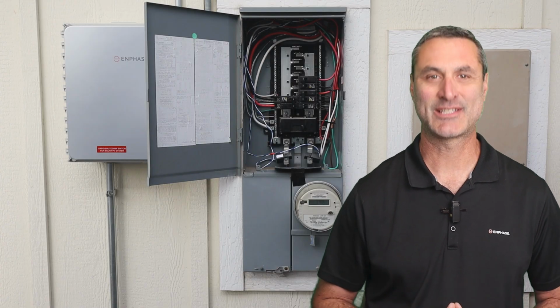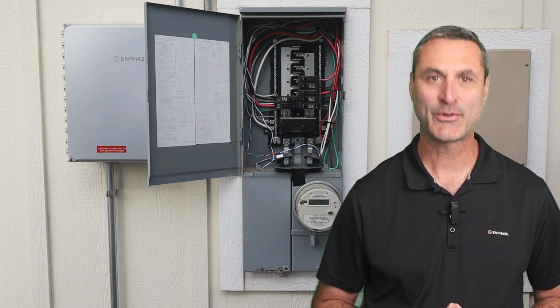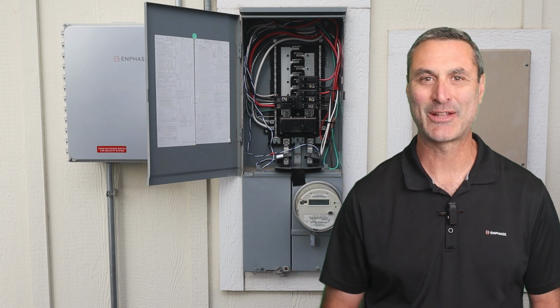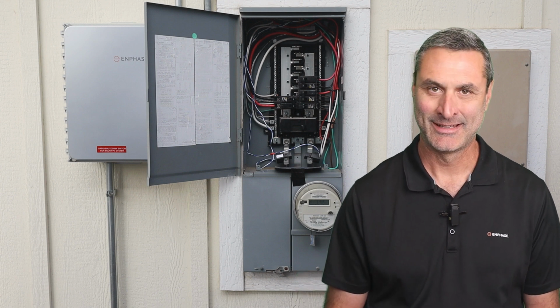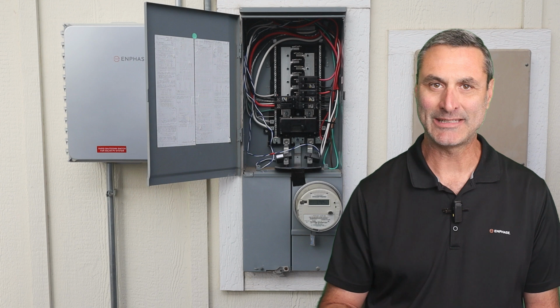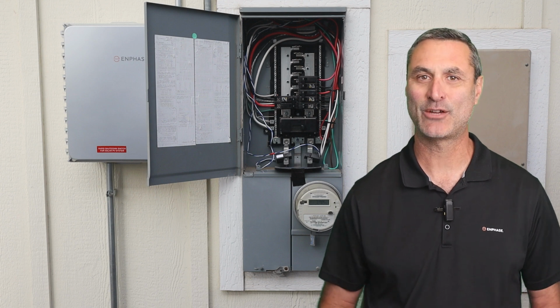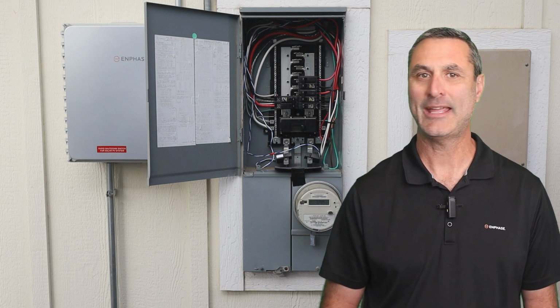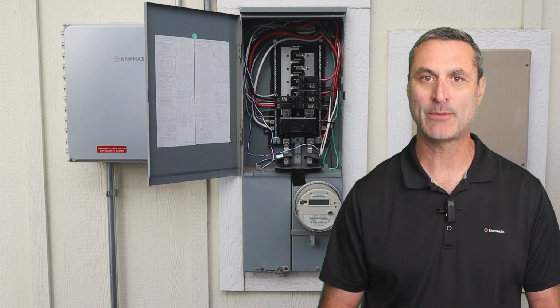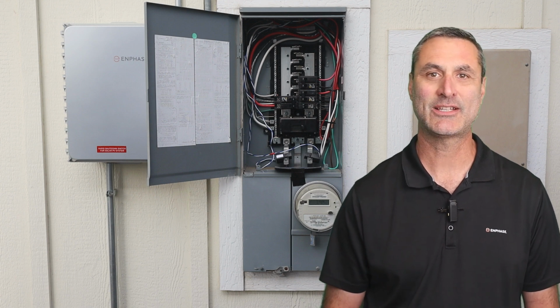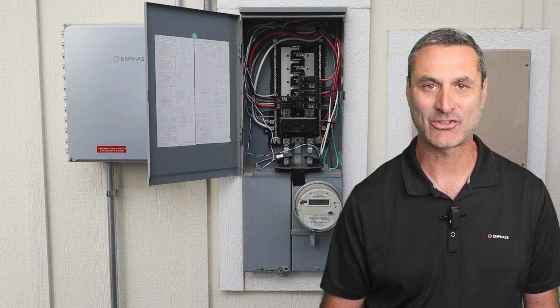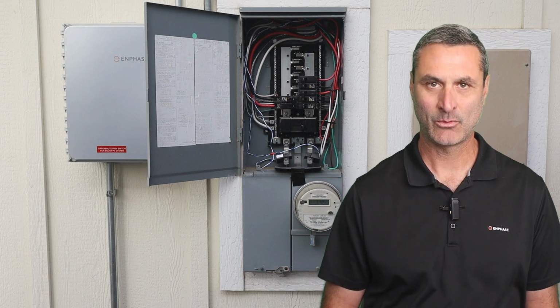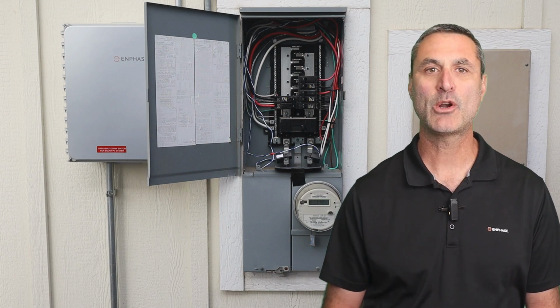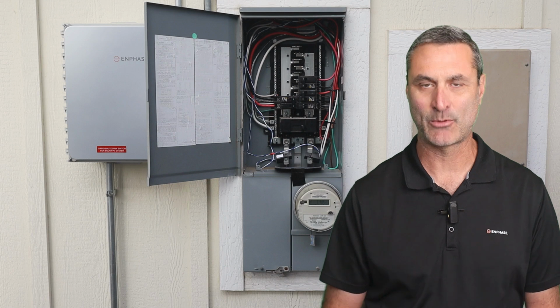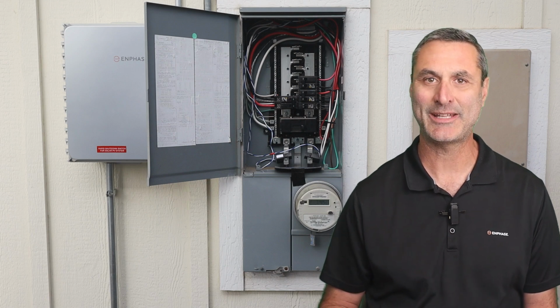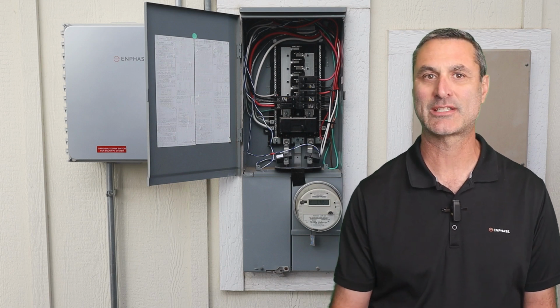Let's review the key benefits of busbar overload control. First, the homeowner will save thousands of dollars by avoiding a main panel upgrade. Since the power of solar and battery won't be limited, the homeowner will maximize self-consumption of solar power. And California homeowners can earn the maximum possible bill credits by selling stored energy in the battery at the highest rates. In summary, with Busbar Overload Control, the homeowner will get every bit of bill savings they expect from their Enphase system, since it's extremely unlikely that the power of the solar and battery system will ever be impacted.